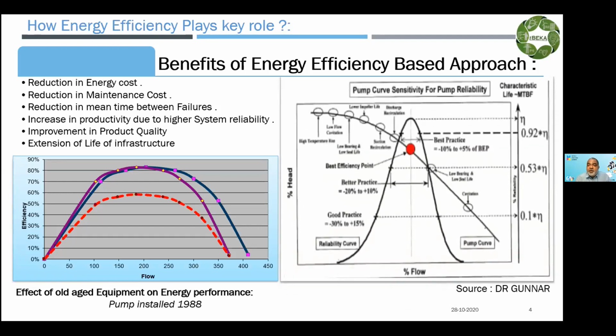Look at the curve where mean time between failure is always a concern for manufacturing processes. If I operate equipment at a best efficiency point, indicated by the red dot, the mean time between failure will be almost closer to zero. That's why if I want to optimize cost, optimize infrastructure, extend equipment life, and improve quality and reliability of production, the only approach is to operate equipment at the best efficiency point.